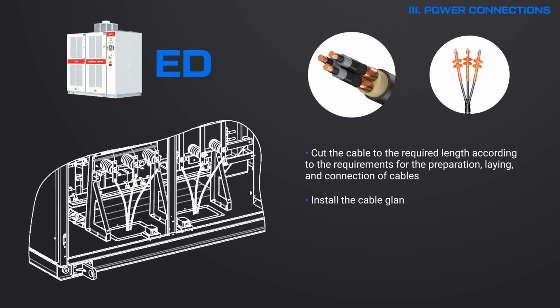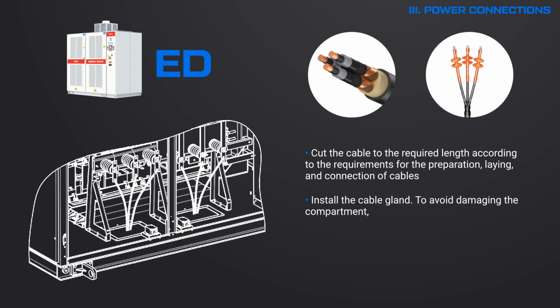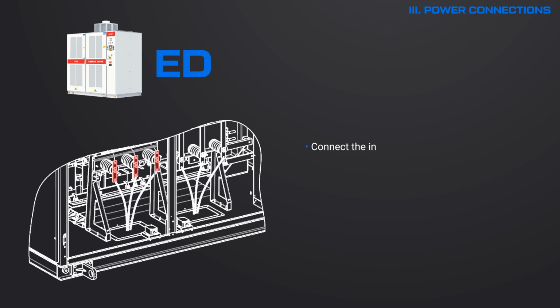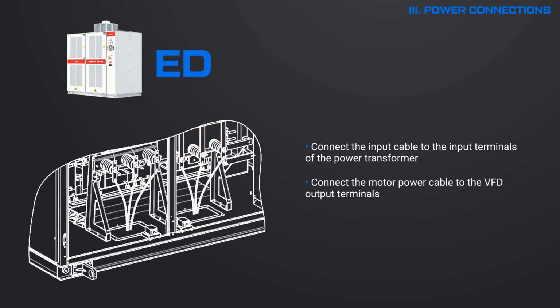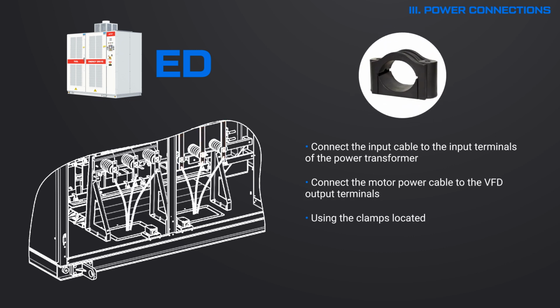Install the cable gland. To avoid damaging the compartment, cut the cables and install the cable glands outside the compartment. Connect the input cable to the input terminals of the power transformer. Connect the motor cable to the VFD output terminals. Using the clamps located near the cable hatch inside the VFD, fix the power cables.